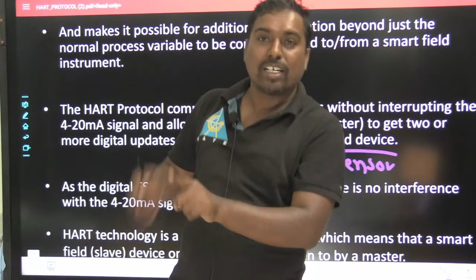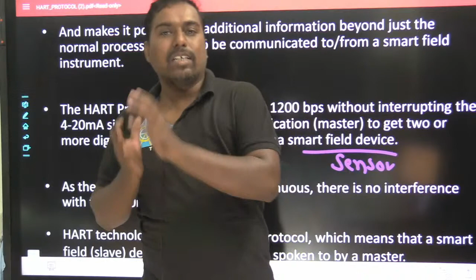So, now one PLC system is there, and I have multiple smart sensors. But remember, all these sensors which I have connected must have a configuration setting to support HART. A HART enabled smart sensor can only communicate with a HART enabled controller. Are you understanding, my dear? A HART enabled smart sensor can only communicate with a HART enabled PLC or HART enabled DCS. Are you getting this point?